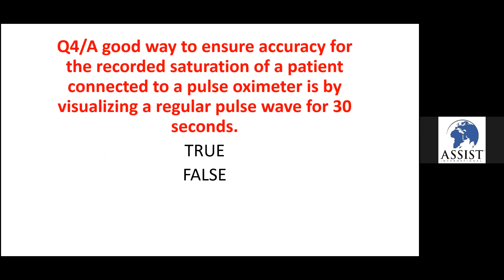So a good way to ensure accuracy for the recorded saturation of a patient connected to a pulse oximeter is by visualizing a regular pulse wave for 30 seconds at least. Is it true or false? So you have to be sure that you've seen it very well. You need to make sure for 30 seconds your wave is normal, a regular wave, sinusoidal wave.